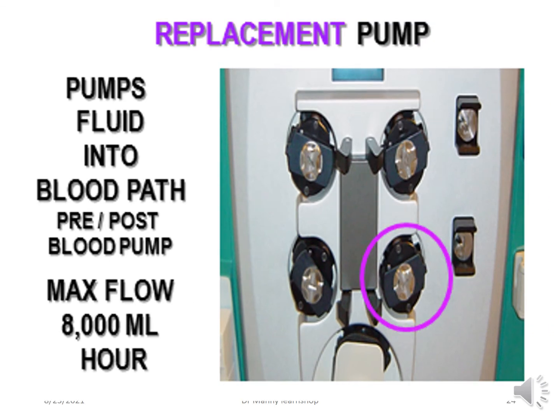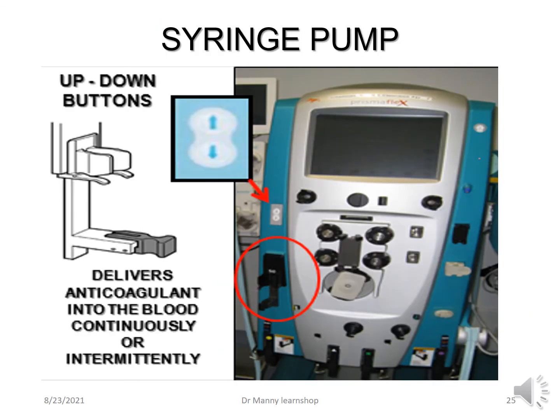Then you've got the replacement pump, and this is a pump that pumps fluid into the blood path either pre or post filter. Maximum flow rate 8,000 mils per hour. It depends on the situation that you're in and what you want to remove or dilute or purify. The syringe pump is to deliver the anticoagulant. This can be done either continuously or intermittently, depending on the physician order.